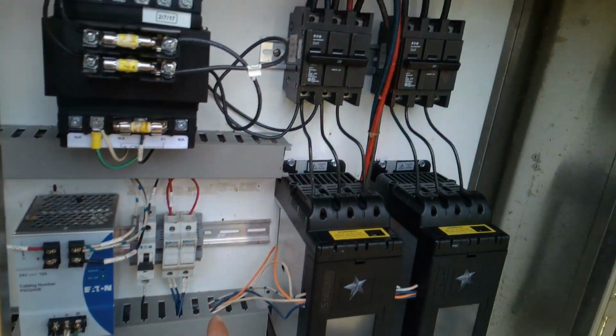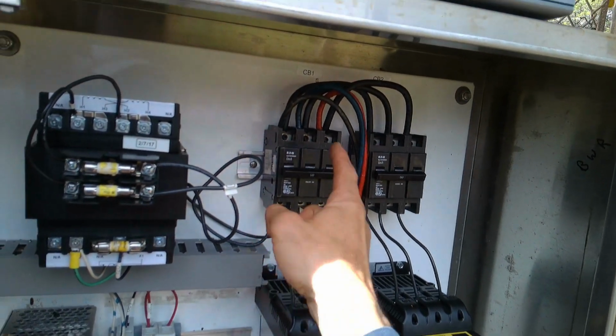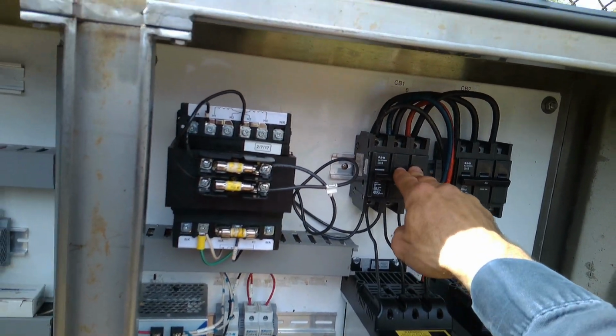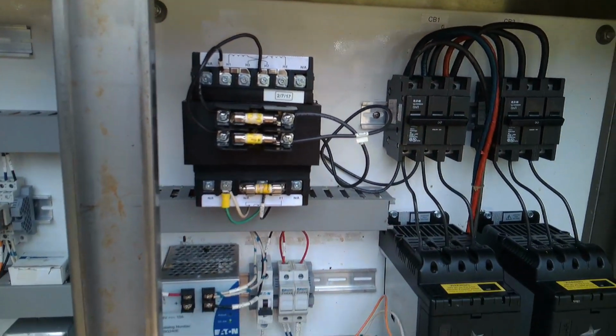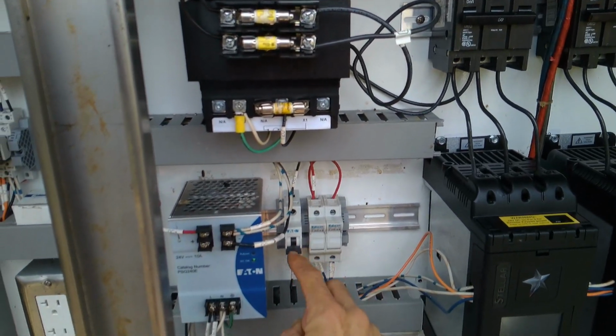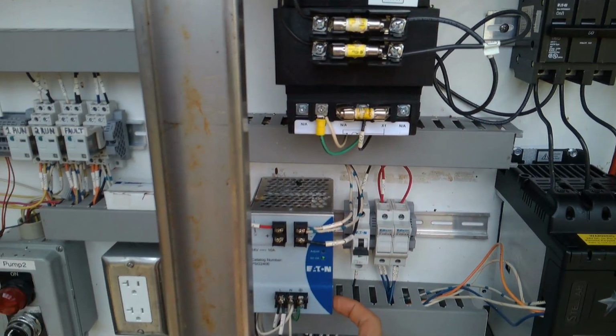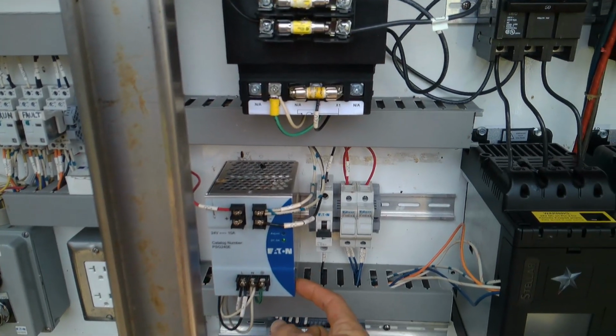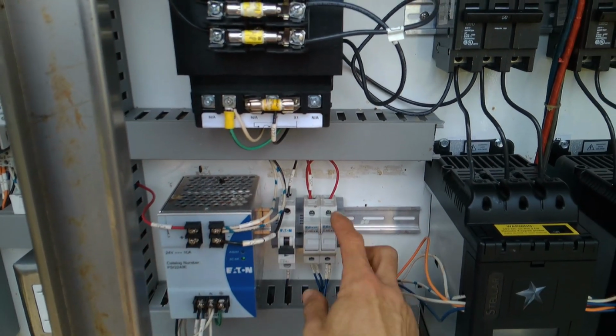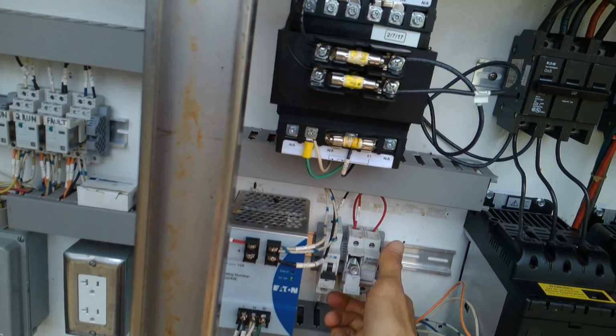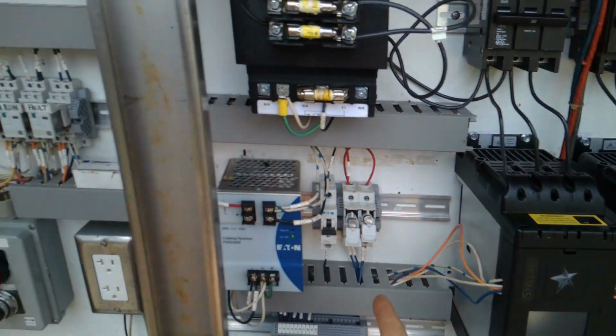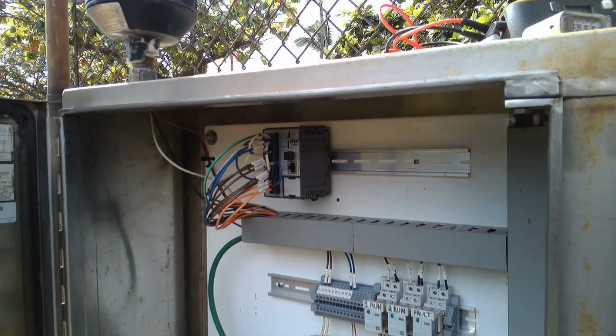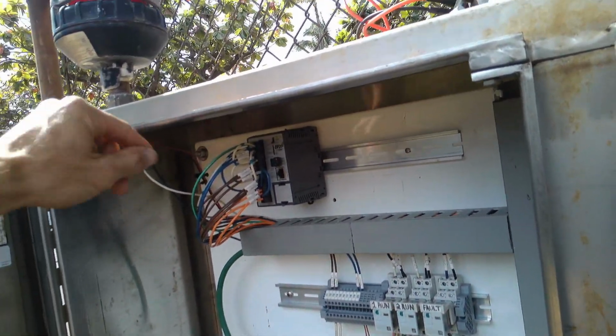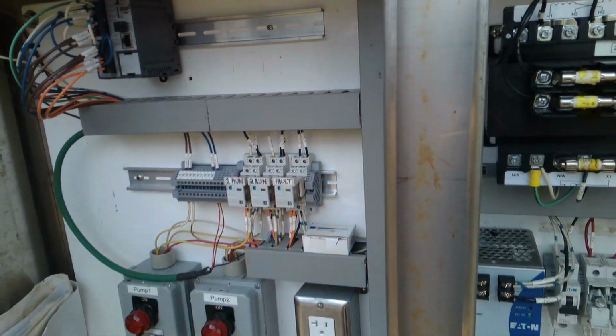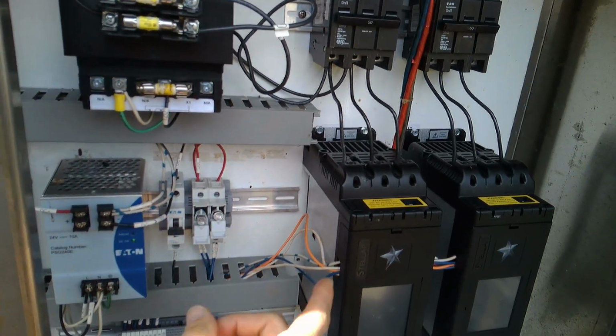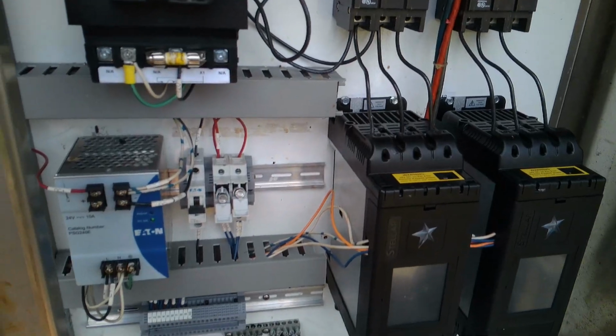Okay, so for starters, when we turn this breaker on, we're taking 208 and making 120 out here. That 120 comes down and goes into this Eaton 24 volt DC power supply. The secondary of that power supply comes to these two fuses, DC1 and DC2. One is running the PLC, DC1. What is DC2 running? DC2 may be running the soft starters.